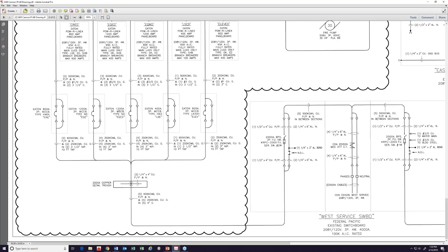The largest device is a 1200. Feeding that from a 2000 gets very tricky. If you look in the table of the manufacturer, you may not see that it selectively coordinates. However, if you look carefully, these are circuit breakers, and this is a fuse. We're able to use the setting because this is a solid state trip unit, and we're able to make sure that the setting will allow the circuit breaker to trip before this fuse in 99% of conditions.